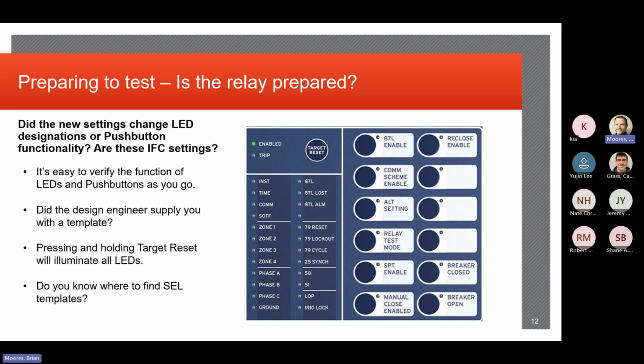So we use that information as we get through the end-to-end testing. So it becomes very valuable at that point, especially to the millisecond, because we want to evaluate, in a power system, milliseconds matter, right? Most of this stuff we want to trip off in a cycle, 2 cycles, and how many milliseconds is a cycle? That's a question. Who has the answer? Like 16.67 or something. There you go. 16 milliseconds is a long time in a power system, especially in fault conditions.